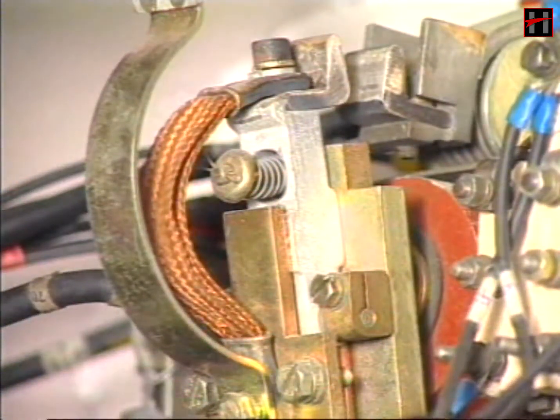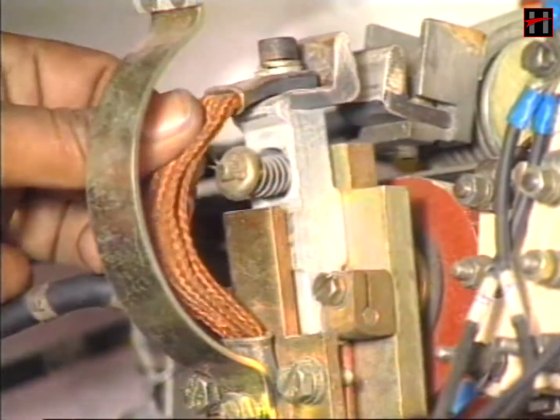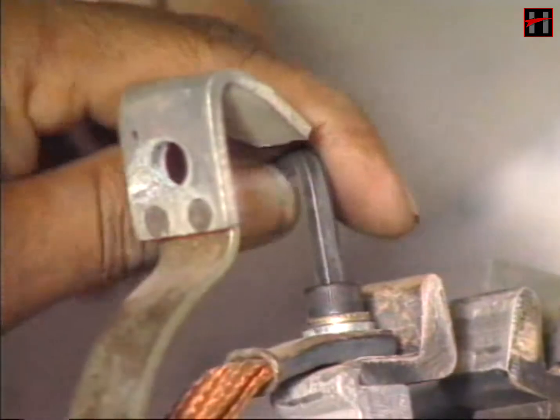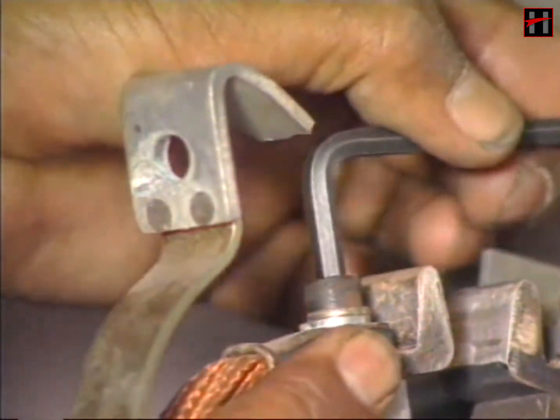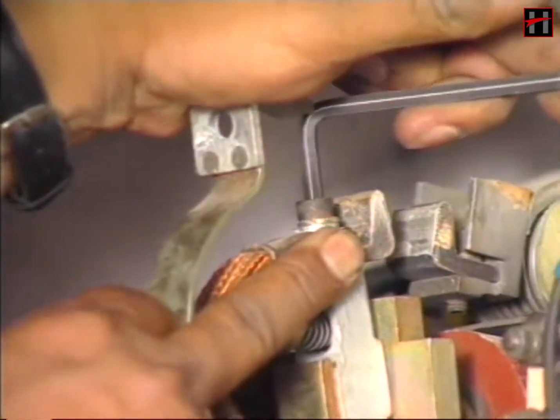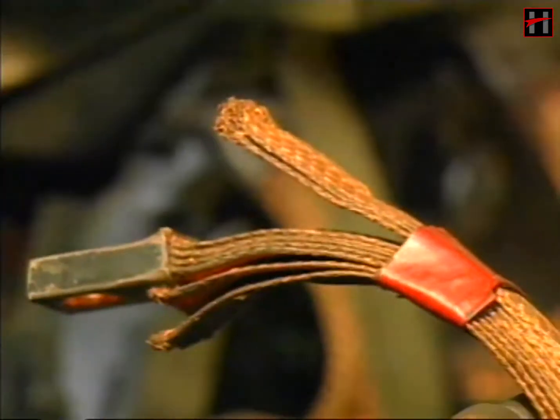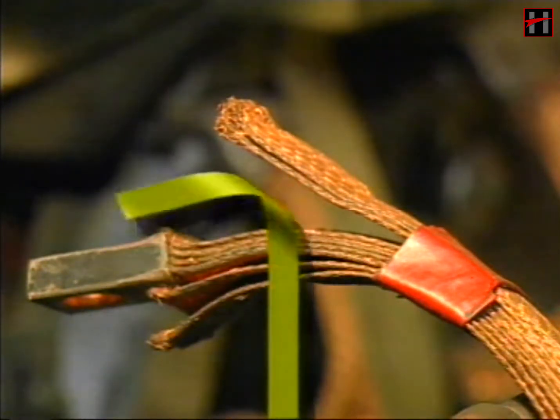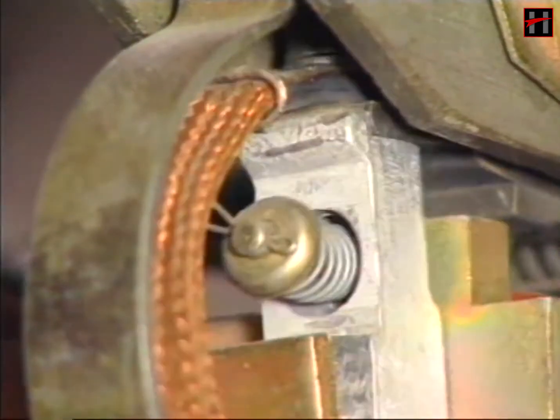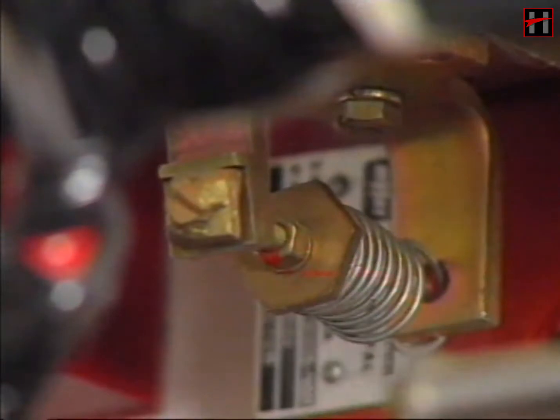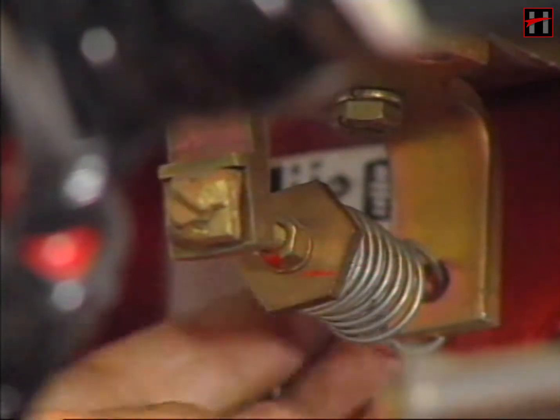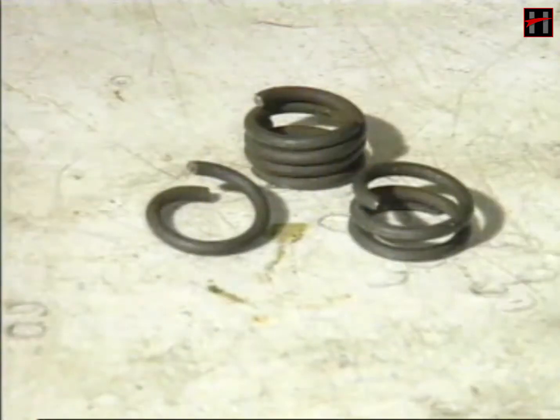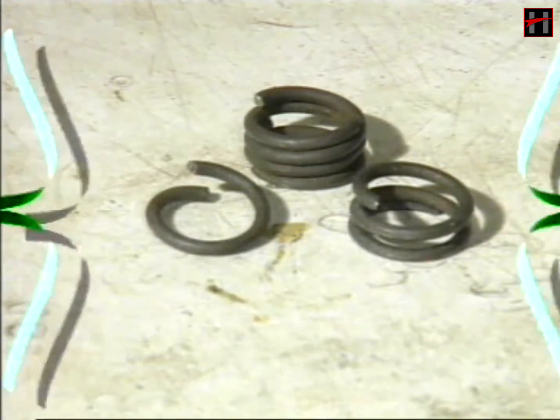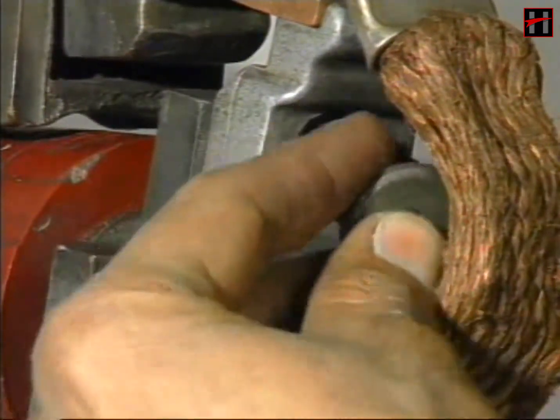Check the shunt of the contactors. All the shunts should be fully tightened at both the ends. If any shunt is showing signs of aging, sulfation, or the copper strands are broken, replace with a new shunt. Check the knuckling spring and the armature spring of the contactors. If the spring is broken or compressed, or the spring tension is not proper, replace with a new spring.